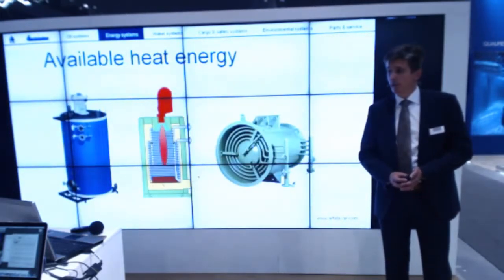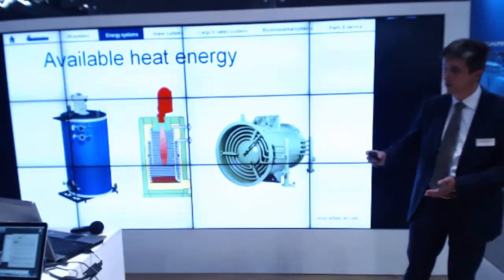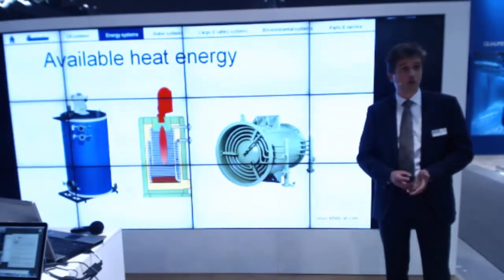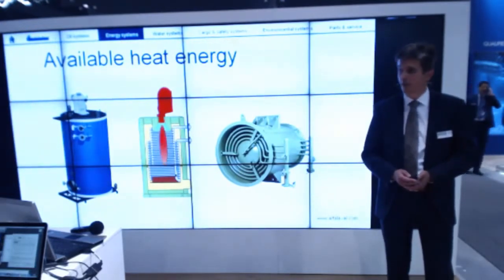The available heat is being produced in an economizer or exhaust gas heater, where the exhaust gas of the engines passes the heating coils and heats up the liquid inside the coils, as well as by an oil-fired heater where a burner is burning oil or gas in order to produce heat energy. This system is automatically controlled by means of a lot of sensors measuring flow and temperature inside the system and starting and stopping the burner and the pumps where needed.